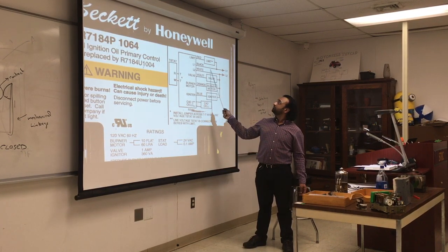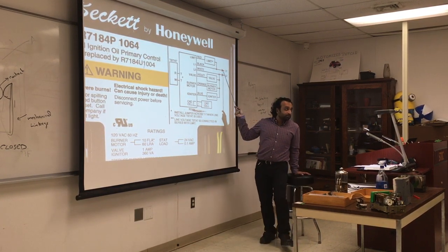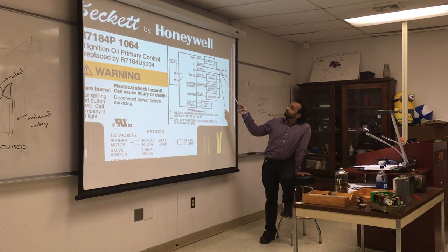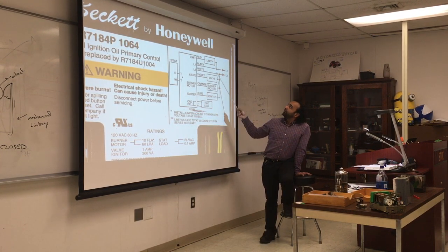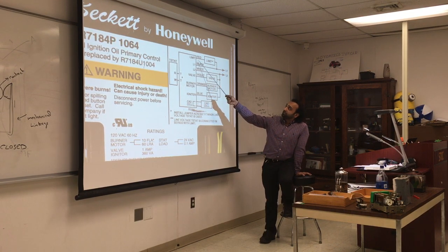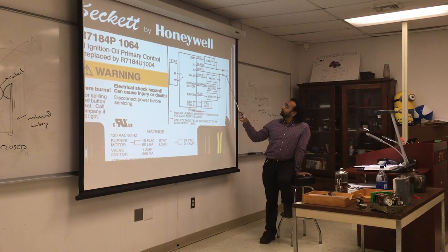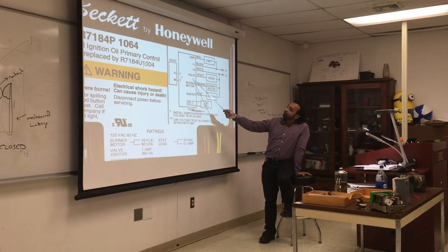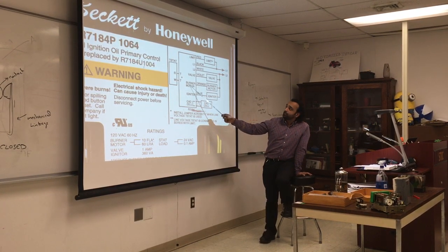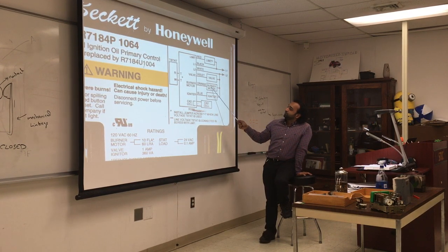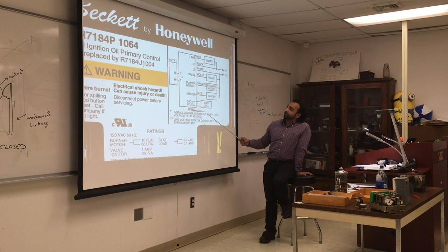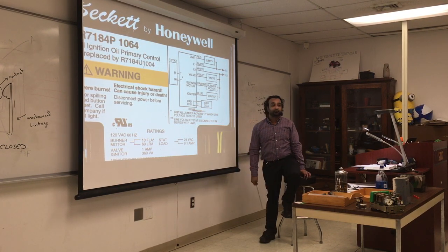L1, black wire coming from L1, which is what? Hot, right? Red line is connected to L1 as well. So same thing. White, neutral. Valve is a violet coming out of this box, or the valve, the neutral. Burner motor, orange, neutral. Blue, neutral. Cad cell goes to cad cell. TT is thermostat, and we're done.